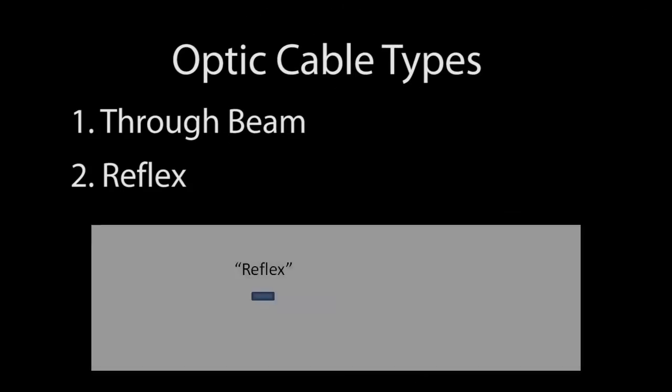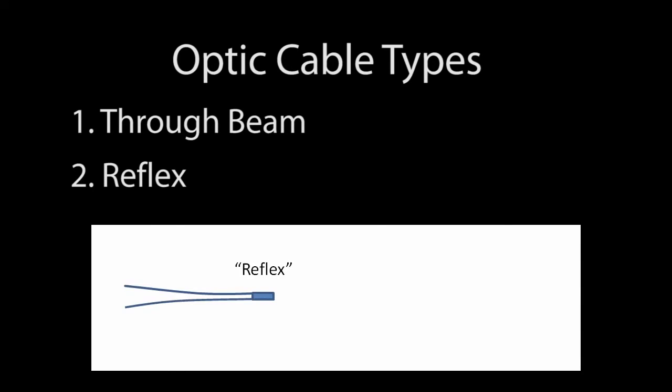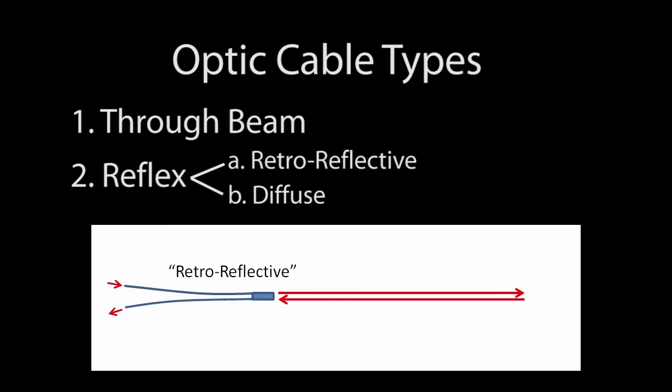The reflex cables have both transmit and receive cables in the same head. One shoots the light out, the other receives the light reflected back. Some folks break that up into retroreflective and diffuse. Retroreflective works like a through beam. The amplifier expects to see light from the reflector and when an object breaks that beam, the light goes away and triggers the sensor. So we also call that dark on because the output gets triggered when the object blocks the beam.